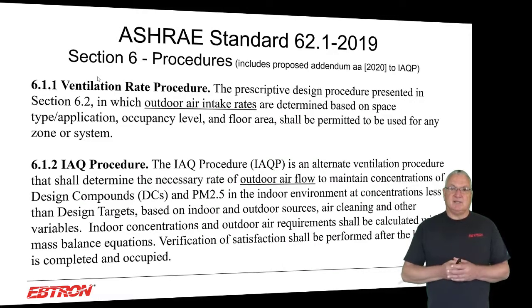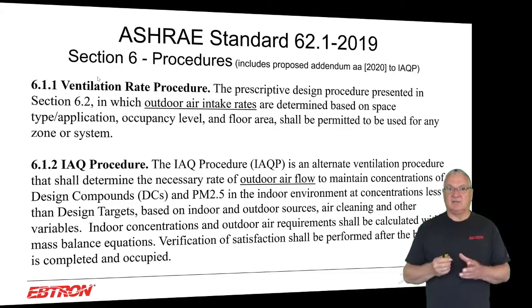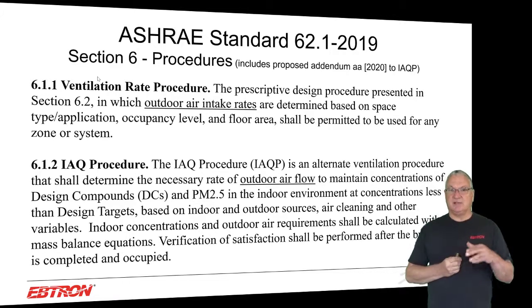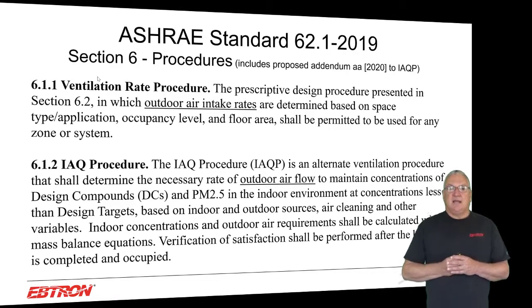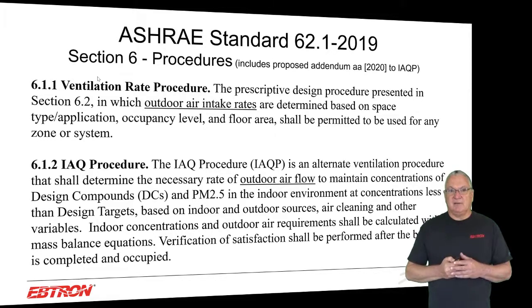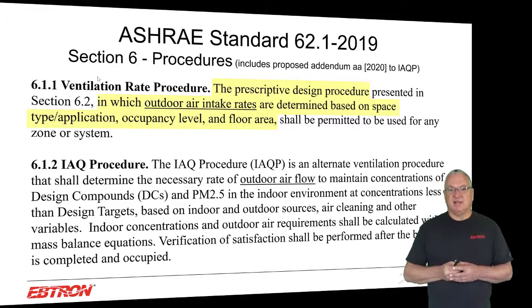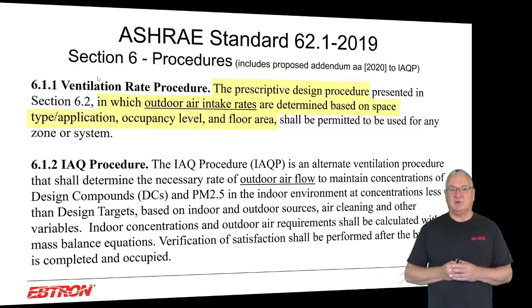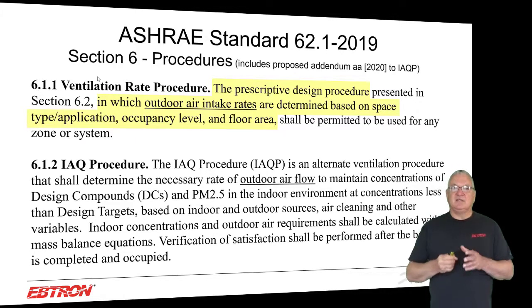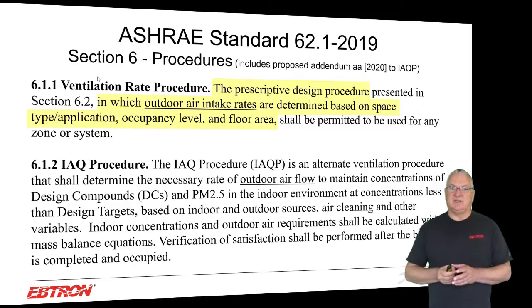Going back to Standard 62 — the ventilation rate procedure is very prescriptive. It's a prescriptive design procedure in which outdoor intake rates are determined based on space type, application, occupancy level, and floor area. It's not really subject to interpretation.